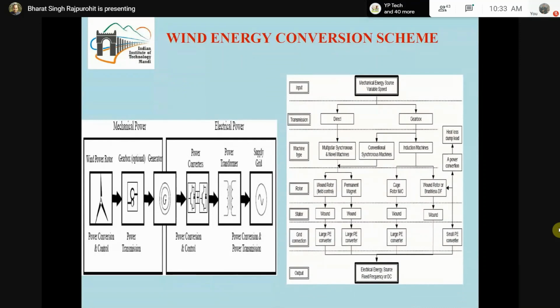Once the power comes from the generator, certain generators, based on their configuration, can be connected directly to the supply grid and transfer the power. But some generators generate power that does not match the grid voltage and frequency. That needs to be processed through power electronic converters, which convert the generated AC power into AC suitable to be connected to the supply grid. And to match the voltage level, power transformers are generally used.